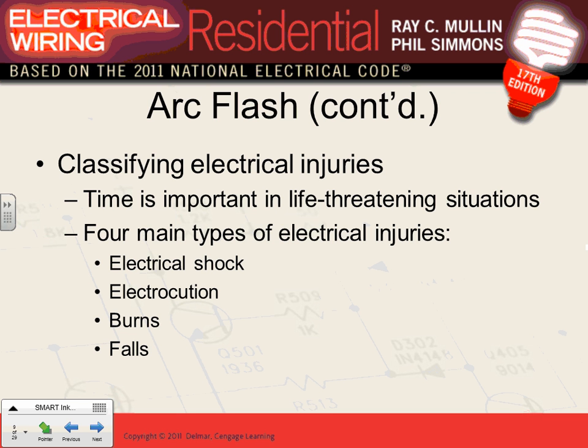You might be thinking, when we start doing power analysis later on, you guys are going to do arc flash analysis for me using the software. You'll put in a current limiting fuse and the arc flash is at this level, then remove it and put a non-current limiting fuse, and the arc flash is at that level. You'll see with the calculation how the faster the fuse opens and the smaller the current, the less big ball of fire is going to chase you in an arc flash. So it's a big deal.